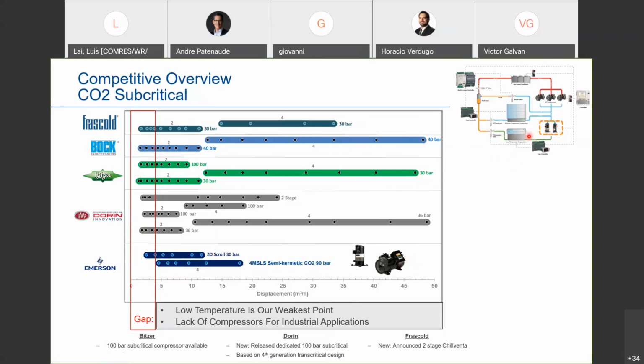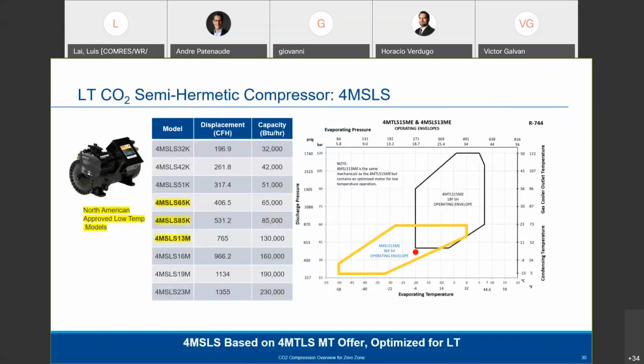And some designers are doing that so that they don't have to add extra mitigation to the system to make sure that the pressures don't exceed the pressure relief values. And you see more of that in industrial, but commercial is starting to move that way as well. Higher standstill pressures are being looked at. And here's one way to do it.